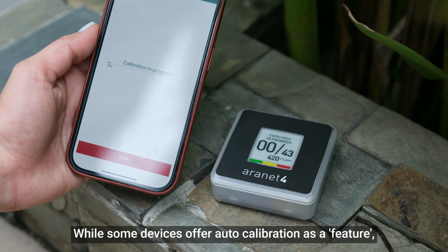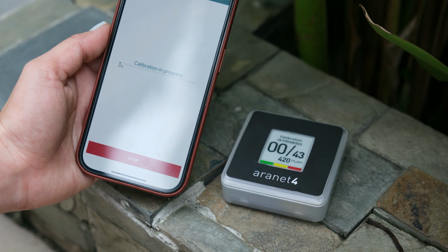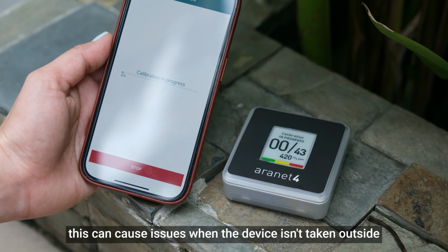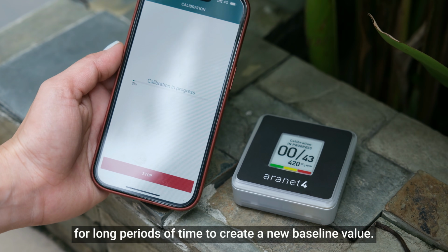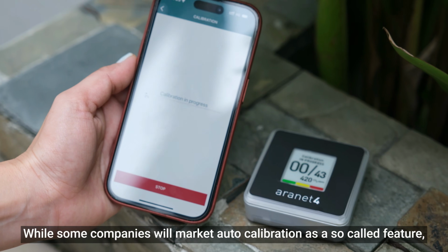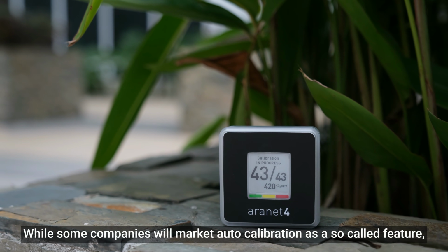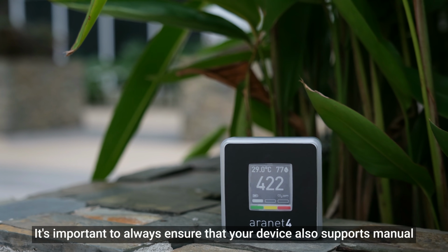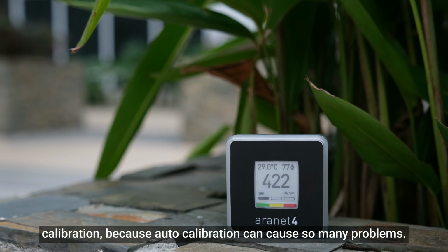While some devices offer auto-calibration as a feature, this can cause issues when the device isn't taken outside for long periods of time to create a new baseline value. While some companies will market auto-calibration as a so-called feature, it's important to always ensure that your device also supports manual calibration, because auto-calibration can cause so many problems.